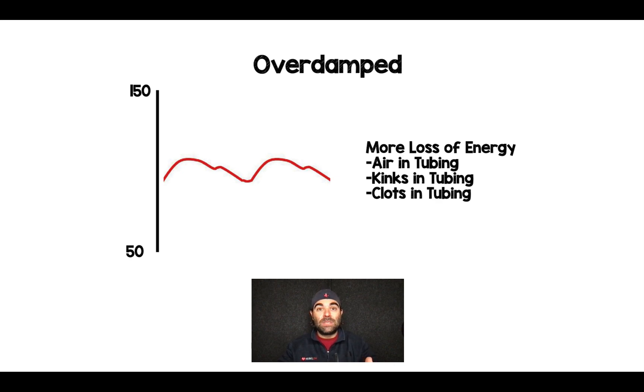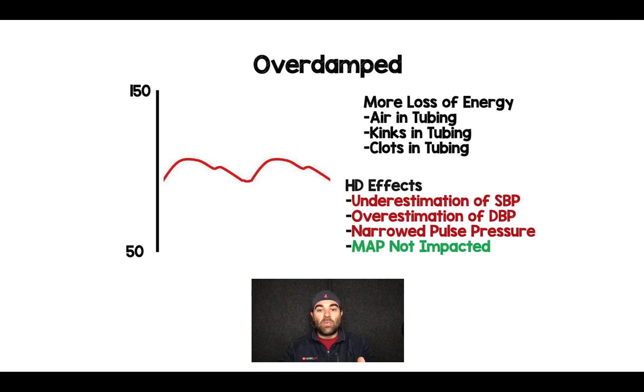When you have an over-damped arterial line waveform, it's going to look super small, because there's something in the line that's causing more loss of energy. This could be things like air bubbles in the tubing, kinks in the tubing, or little clots in the tubing. All three of these things will damp or reduce the waveform. Why is this important? Because there are hemodynamic effects — it's going to underestimate your systolic blood pressure and it's going to overestimate your diastolic blood pressure. You're going to see a narrowed pulse pressure.